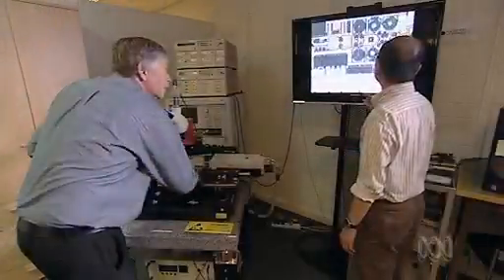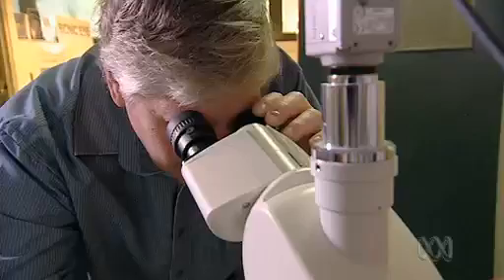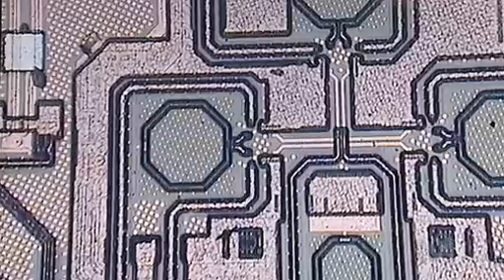The sort of image that people receive is in fact quite different. With electrical stimulation, people perceive what are called phosphenes — these are flashes of light in the visual field. Each electrode can deliver one phosphene, or pixel if you like. So with 100 electrodes on the first implant, the visual information will be very limited.